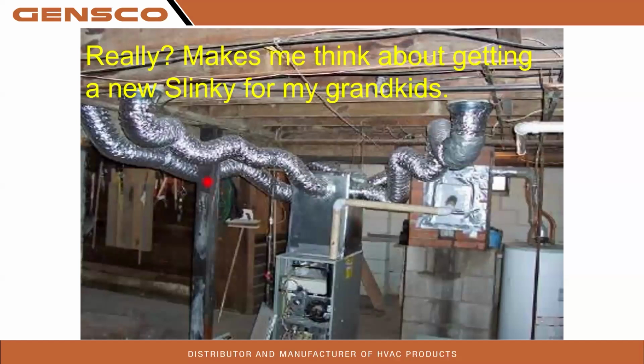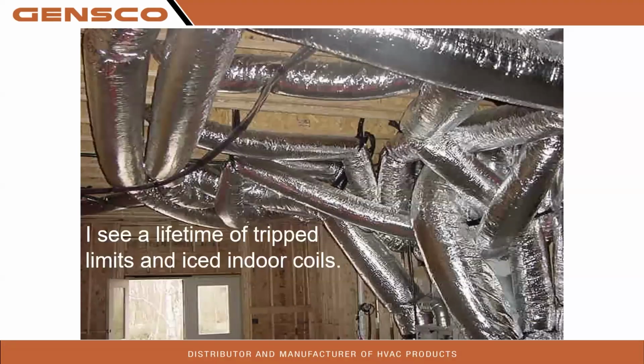Yeah, I mean, this stuff should always be trimmed and as straight as possible, and make sure that you have a good 90 going into the boots. All right, this could be cleaned up pretty easy. Look at all this room up down here in the basement. And the pipes even slope downward. These are great pictures of what not to do. I've seen this in crawl space where the guys just don't want to cut it to fit. Flex duct's a lot faster. The good thing is the inspectors are making the guys correct it most of the time.